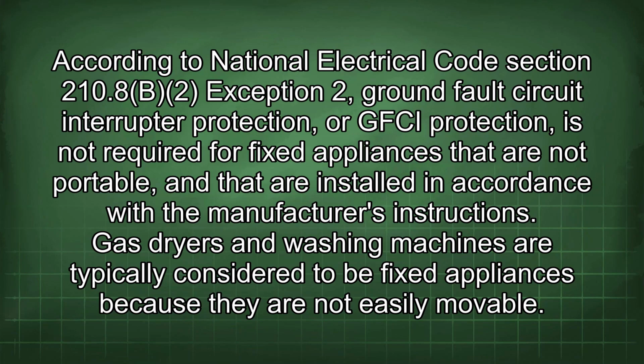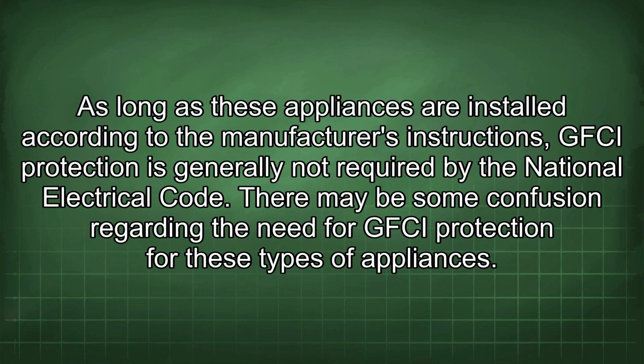According to National Electrical Code Section 210.8(B)(2) Exception 2, ground fault circuit interrupter protection, or GFCI protection, is not required for fixed appliances that are not portable and that are installed in accordance with the manufacturer's instructions. Gas dryers and washing machines are typically considered to be fixed appliances because they are not easily movable.